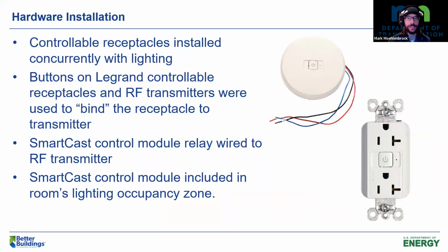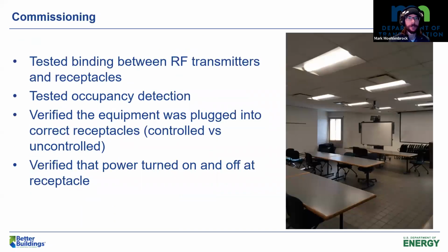So basically how the installation went is that the electricians installed the controllable receptacles concurrently with the lighting. There's a button on both the receptacle and on the transmitter that is used to bind the receptacles to the transmitter. So I think the commissioning process was basically hold down the button on the transmitter and then go find all of the receptacles that you want paired with that transmitter, hit the button on them, and then go back and hit the button again on the transmitter, and they should be bound. So when that transmitter gets the control signal from the SmartCast relay, it will turn the receptacle on and off. Next slide, please.